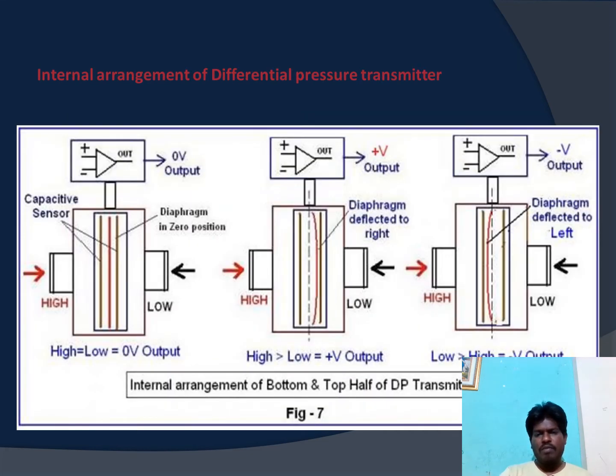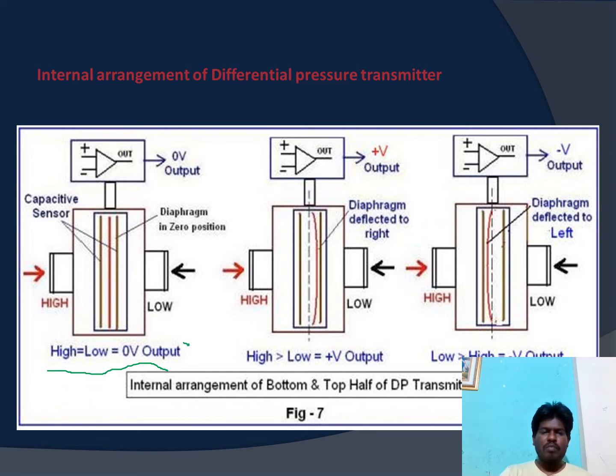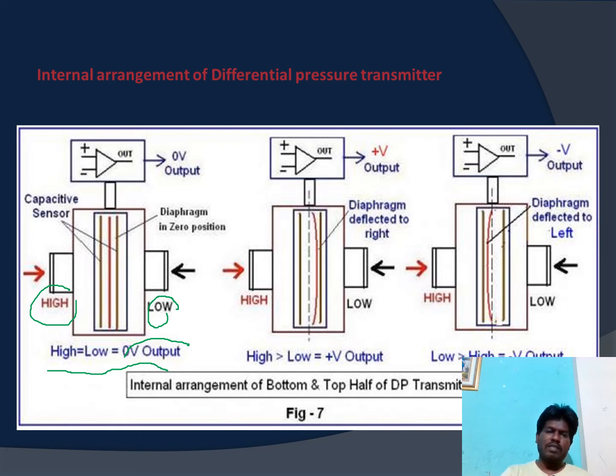There are three different cases we will look at internally in the differential pressure transmitter. In the first condition, when the high pressure and the low pressure are equal, the output will be zero volts. When both terminals have the same pressure, there is no deflection of the diaphragm and therefore no change in capacitance. Since capacitance is directly proportional to the output, the output voltage is zero.